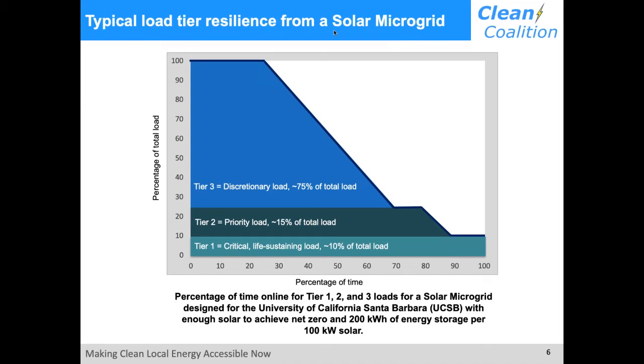Based on these typical loads, this slide shows the percentage of time we can keep tier one, two, and three loads online for a typical solar microgrid in California that decides to achieve net zero energy. As the chart shows, for a typical solar microgrid, tier one loads can be kept online 100% of the time. That's how we size them. Tier two loads can be kept online at least 80% of the time, and tier three loads can be kept online at least 25% of the time. And this is in the worst solar conditions, so if there's a lot of sun, they can be kept online even longer.